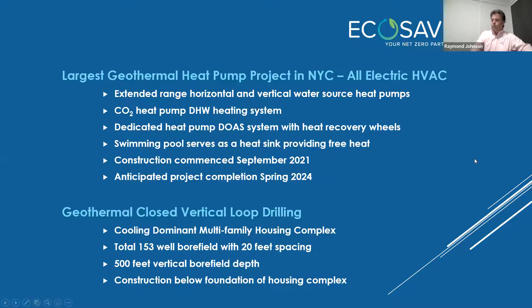Again I apologize for the eye chart, but a couple of things I wanted to focus on: community heat loops provide scale to reduce installation costs. As a designer of systems, we did not have to oversize for worst case conditions as much, so there are economies of scale we were able to take advantage of. Secondarily, we have diverse loads, which enables us not to always reject heat to the bore field or take heat from it, but to transfer it with diversity, with different peaks from different users. That helped us optimize bore field size and reduce initial costs.